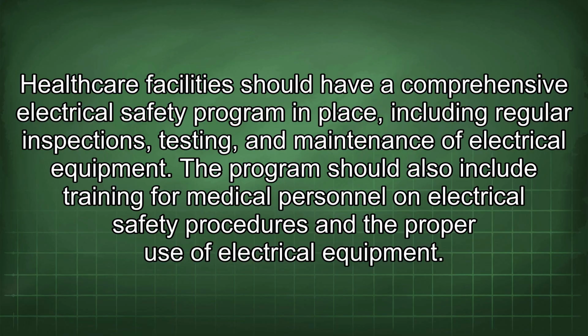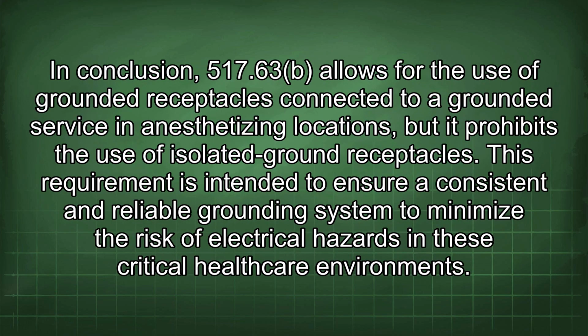Healthcare facilities should have a comprehensive electrical safety program in place, including regular inspections, testing, and maintenance of electrical equipment. A program should also include training for medical personnel on electrical safety procedures and the proper use of electrical equipment. In conclusion, 517.63 allows for the use of grounded receptacles connected to a grounded service in anesthetizing locations, but it prohibits the use of isolated ground receptacles.